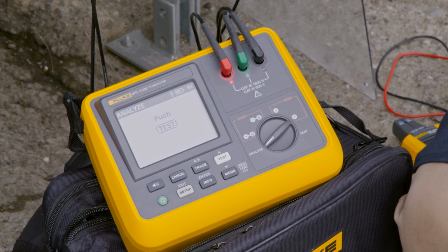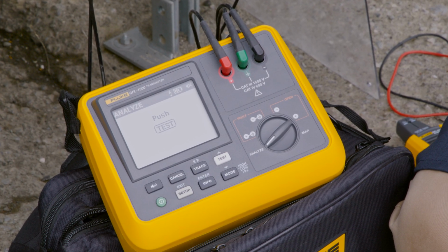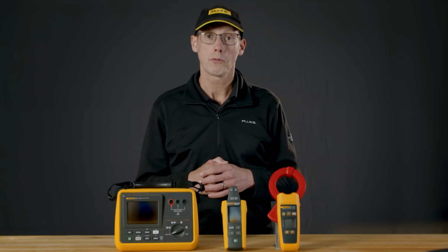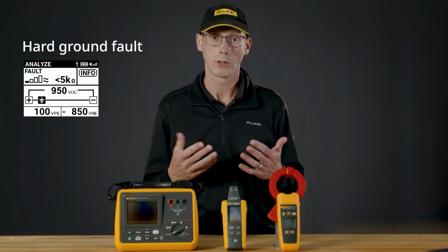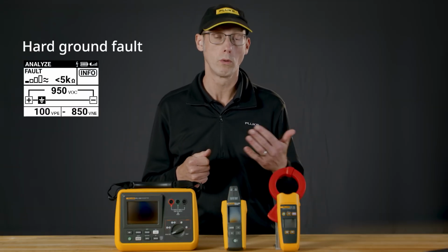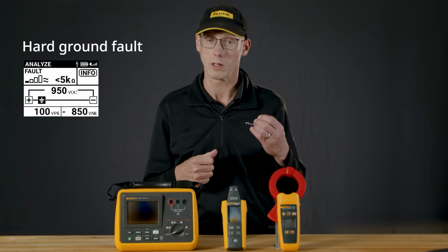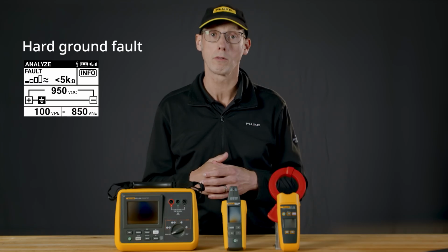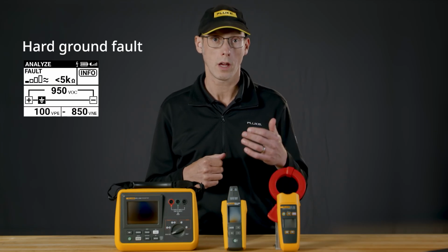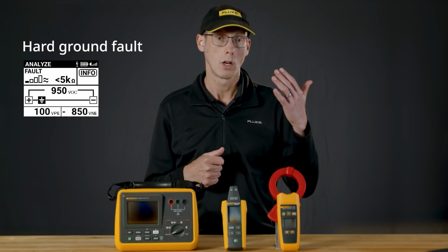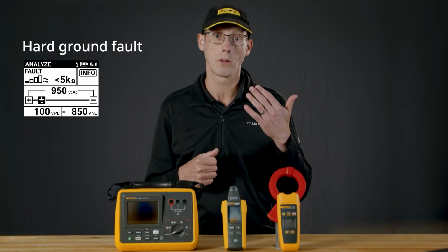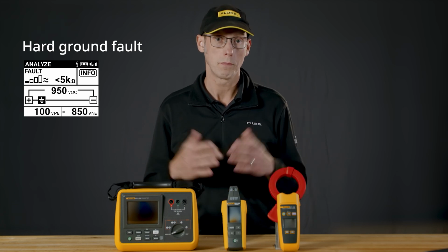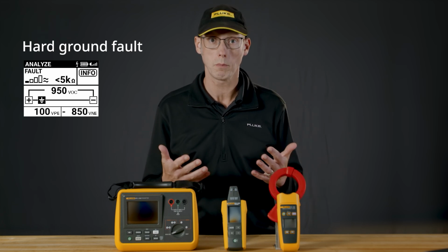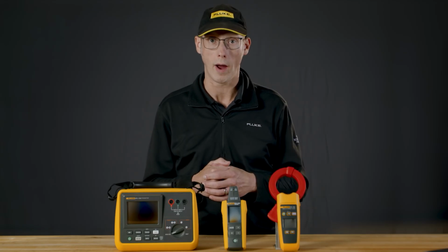Analyze mode will return 4 different possible results. The first one is a hard ground fault. This is a fault that has low resistance to ground, so it typically would be a solid ground fault where there is a permanent connection to the ground that is always present. This is one of the easiest ones to find because of that low resistance to ground.